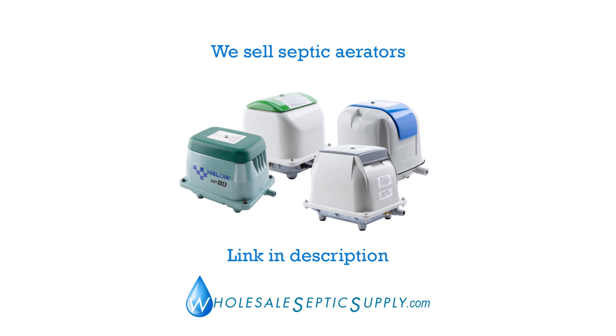And then you have these two which are rare earth magnet pumps. These aren't as popular — people aren't as familiar with them — but they run cooler and they draw a lot less power: 1.3 amps, 1 amp. Because they run cooler, you're going to get a longer life out of them — probably four to six years trouble free, no issues.